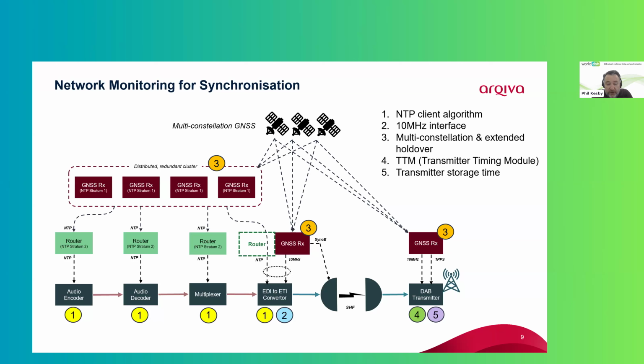However, if the transmitter loses its synchronization, then that offset will start to drift, and at that point it signals that condition to our operation center, and we know that the synchronization, or the timing reference to that transmitter, has become untrustworthy.